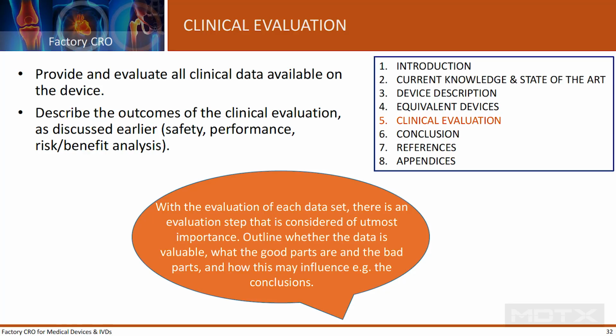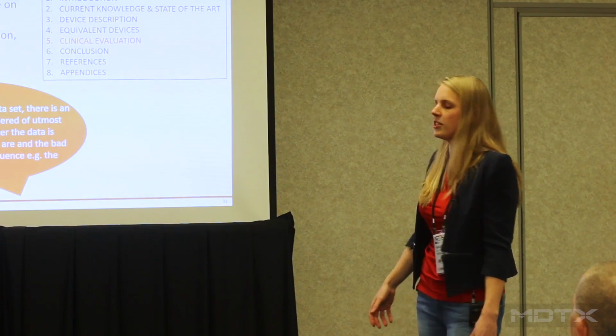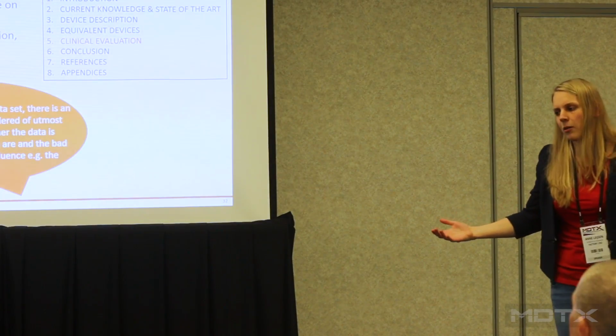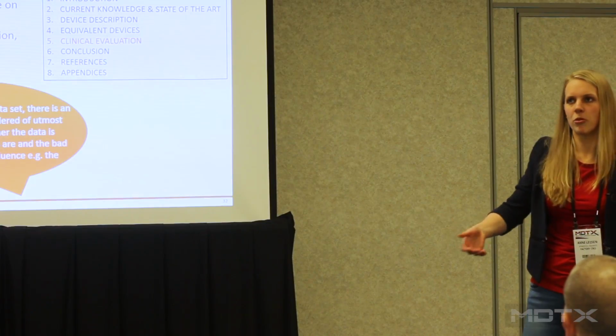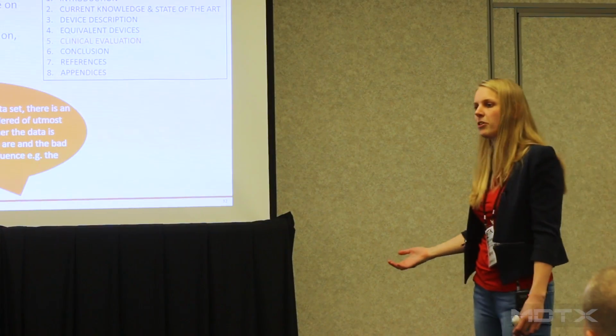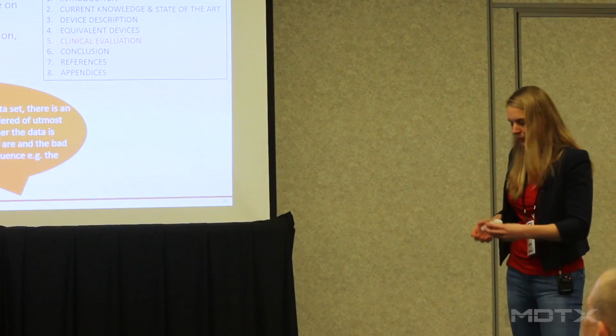And make sure as well that you don't only provide the data and just put it in there, but also evaluate and appraise the data. Tell whether it's valuable or not, or which parts you think are useful and which are not. For example, when data is from a period when you had a different design of your device, but it's not really about the design, more about biocompatibility, it might still be useful, but do outline it so the notified body doesn't have to guess that themselves.